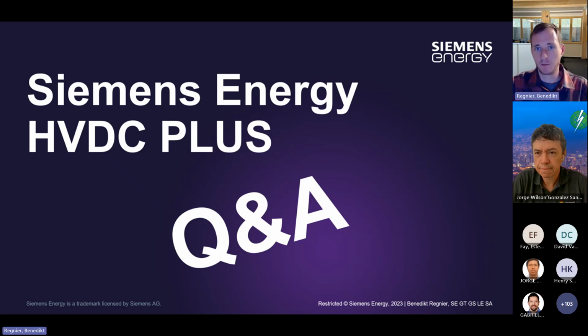It depends a little bit. We're having these discussions just now with some clients. They have a very low power, but they want a lot of functionalities. They want it in the bipole configuration. So if you look at the price per megawatt, the lower you go, the more expensive it is, because there are a lot of things which are fixed, like the control system. The size of the converter is related to the DC voltage. So if you say, I definitely want 500 kV because I want very low losses on the line, but only want to transmit 300 megawatts, then the converter is heavily oversized for the voltage, which means you need to pay for a big converter, and only the transformer is something that you can play with, where you can save a little bit. But yes, that's the case.